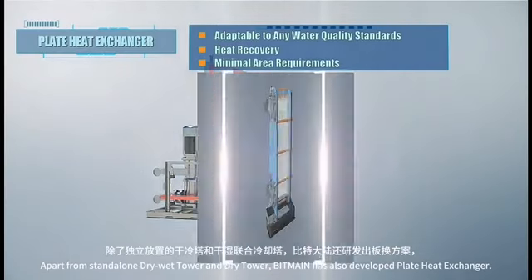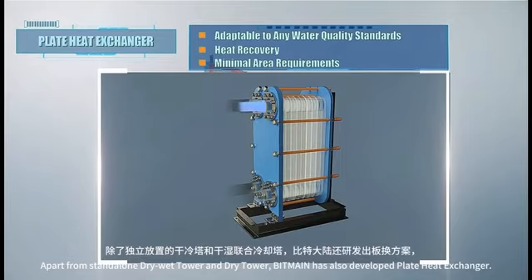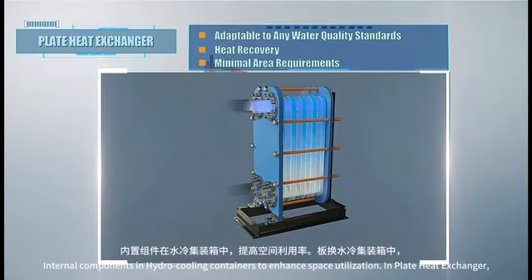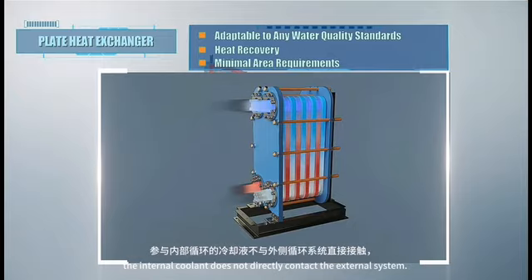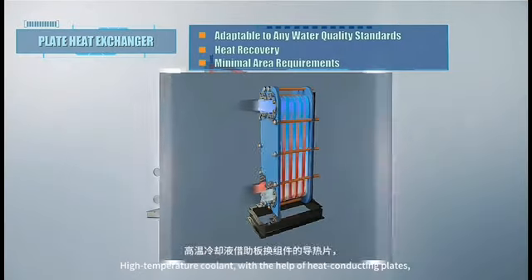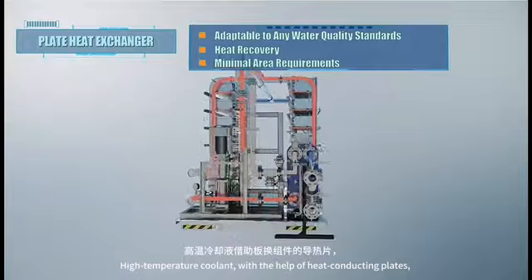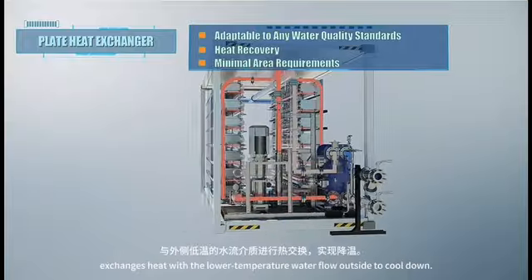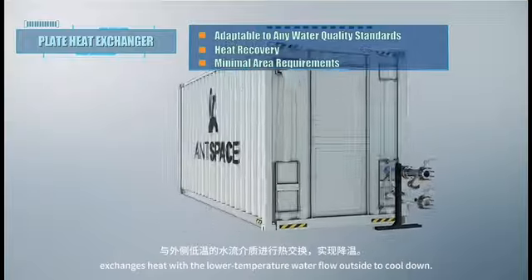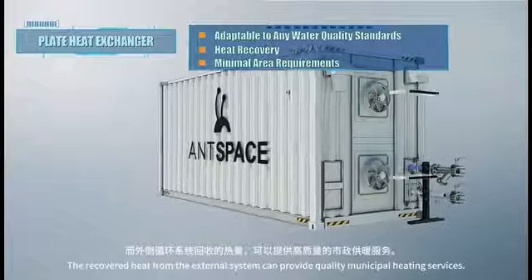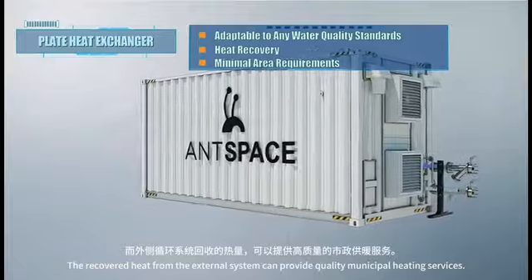Apart from standalone dry-wet tower and dry tower, Bitmain has also developed the plate heat exchanger, internal components in hydro-cooling containers to enhance space utilization. In the plate heat exchanger, the internal coolant does not directly contact the external system. High-temperature coolant, with the help of heat-conducting plates, exchanges heat with the lower-temperature water flow outside to cool down. The recovered heat from the external system can provide quality municipal heating services.